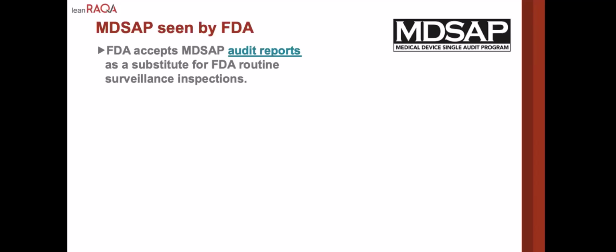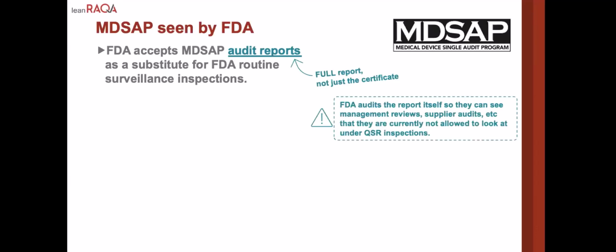FDA will audit the full report, not just the certificate. Now, this is significant because right now, under the quality system regulation, they are not allowed to audit the content of management reviews, supplier audits, internal audits, but they will audit those things in the MDSAP audit report. They do not send these to FDA redacted. So just be aware that this will be a little bit of an open kimono type situation with the FDA compared to the scope of your audits now.